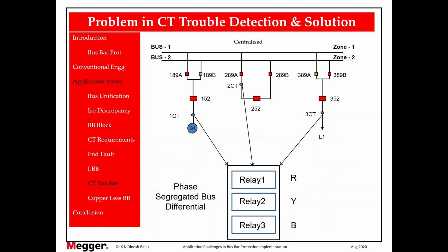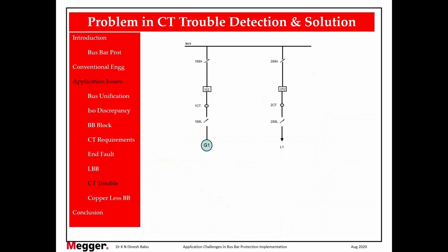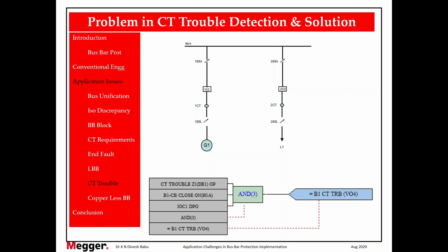But in a centralized arrangement, since it does not have symmetrical components, how can we do this? Let's see how this can be done. A single bus bar, here the logic is this. If there is CT trouble in this zone, along with that, the second input is, is the breaker closed? Yes. The third input is the undercurrent picked up.